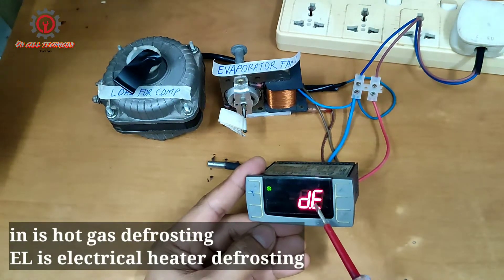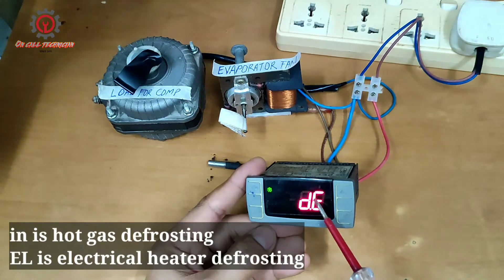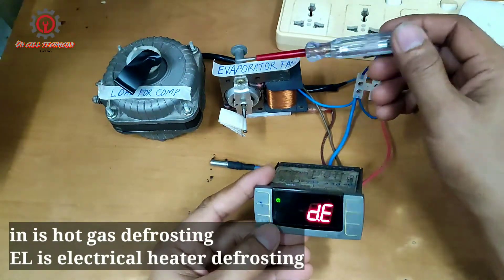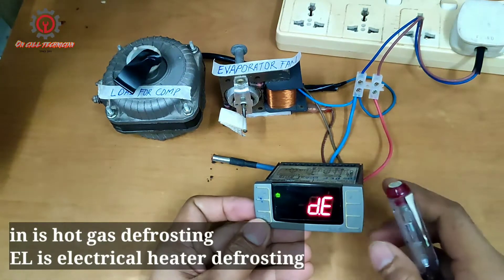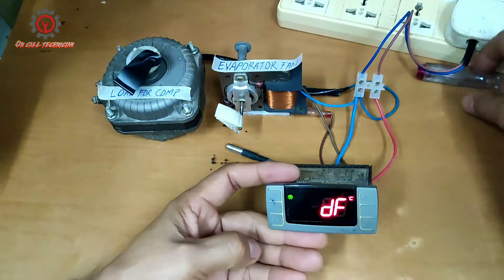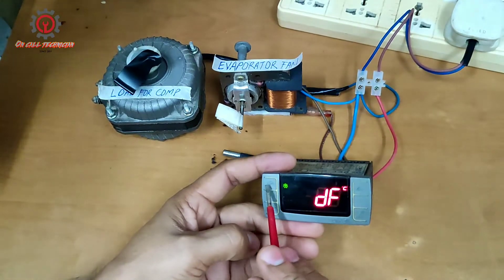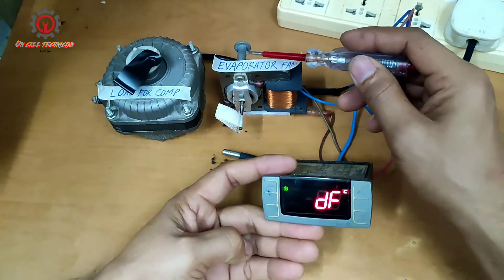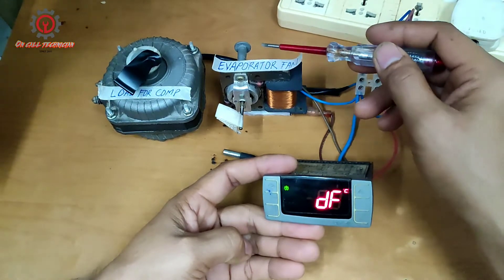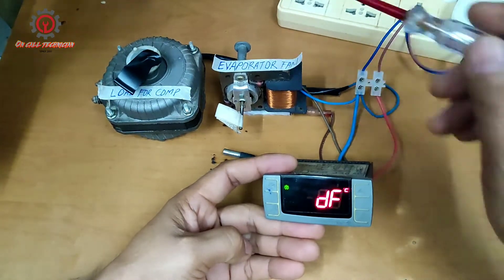We set dF and we're going to select it to electrical. Look what happened — it stopped now. Take note guys, DD should be set to electrical defrosting, not to solenoid.